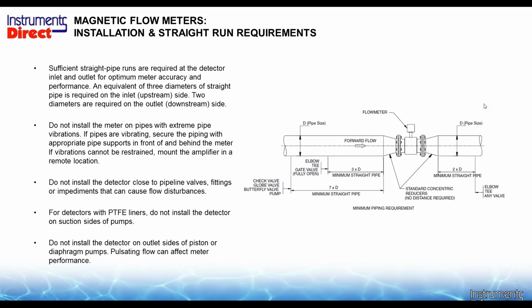How much straight run of pipe do you need for this particular mag flow meter? Generically speaking, from elbow to flow meter, if you have 3 pipe diameters between the elbow and the meter, and 2 on the output of the meter before the next obstruction, you're good for your basic application to meet your accuracy requirements. Should you have something very nasty before your flow meter, like a check valve, a globe valve, a butterfly valve or a big pump, that's a little more disruptive than a 90-degree elbow, believe it or not. You need a little more straight run of pipe. In that case, we'd like to have about 7 pipe diameters prior to the flow meter. People ask all the time about pipe diameter. If I had a 1-inch meter, for example, I'd need a minimum of 3 inches before. Or if I had a 10-inch pipe, I'd need 30 inches before, and so on.